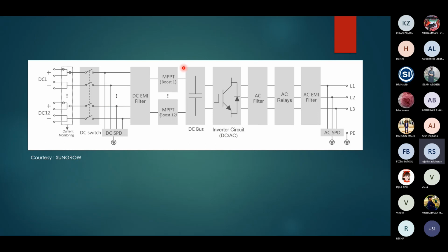Here is the internal circuitry of a standard inverter. You can see that there is a provision where the DC strings are plugged in. Then it requires a kill switch, of course, but usually we never switch this off while it is under load. As I explained, it can create a serious arc. And once this DC energy is coming into the inverter, it requires a surge protection, like in case of a lightning strike or a severe short circuit. It should protect the further circuitries within the inverter's motherboard.